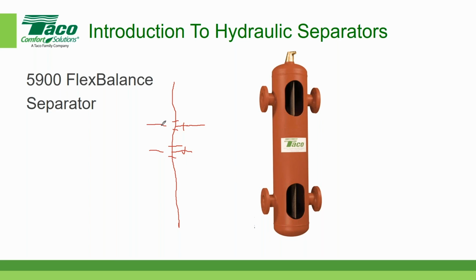So the distance between the T's has to create a pressure drop that is close to 0, which is where the term closely spaced tees comes from. But on the other hand, it also has to have a far enough distance relative to the diameter of the pipe, this diameter right here, so that you don't wind up with unanticipated mixing. So it's not that easy if you're designing it yourself.